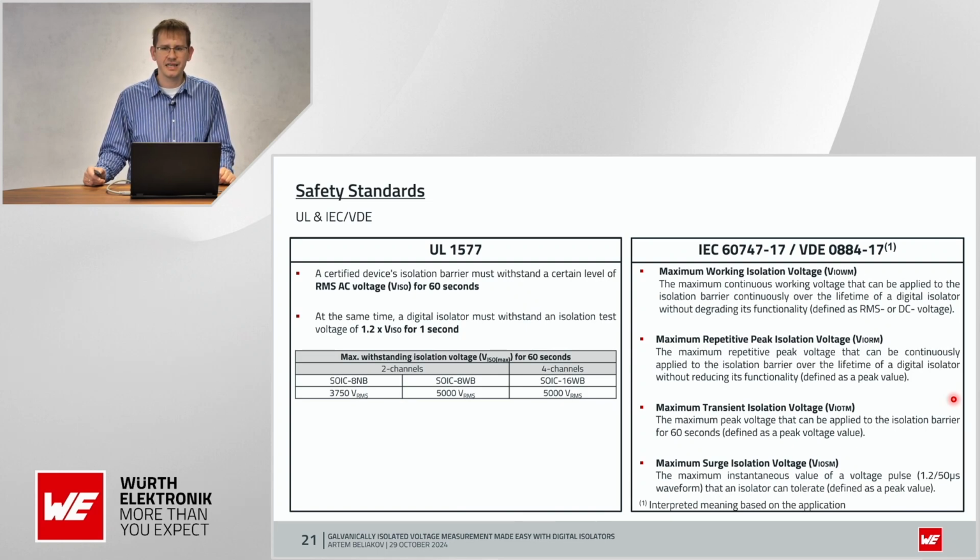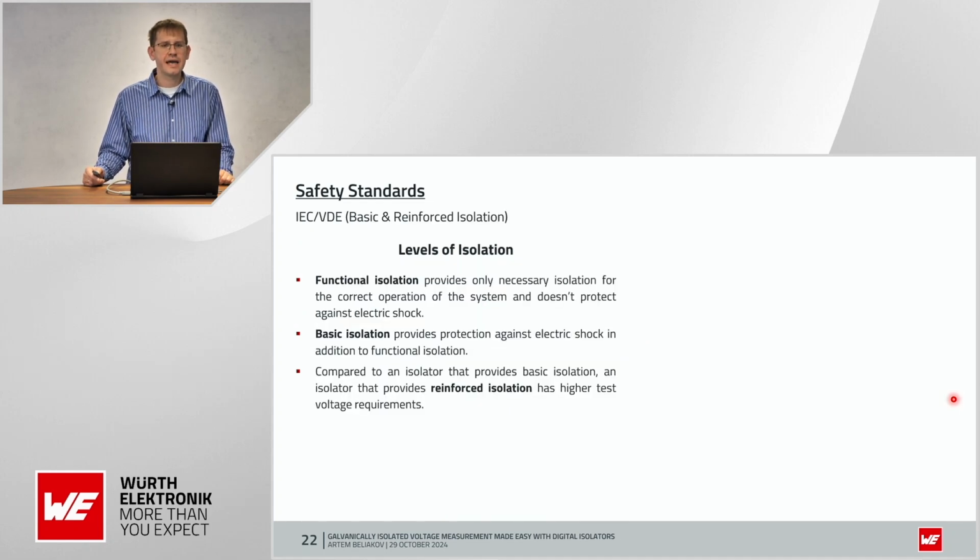And the last isolation voltage on this slide is the maximum surge isolation voltage. This is the maximum instantaneous value of a voltage pulse that an isolator can tolerate, and this isolation voltage is defined as a peak value. On this slide, you can see different levels of isolation.